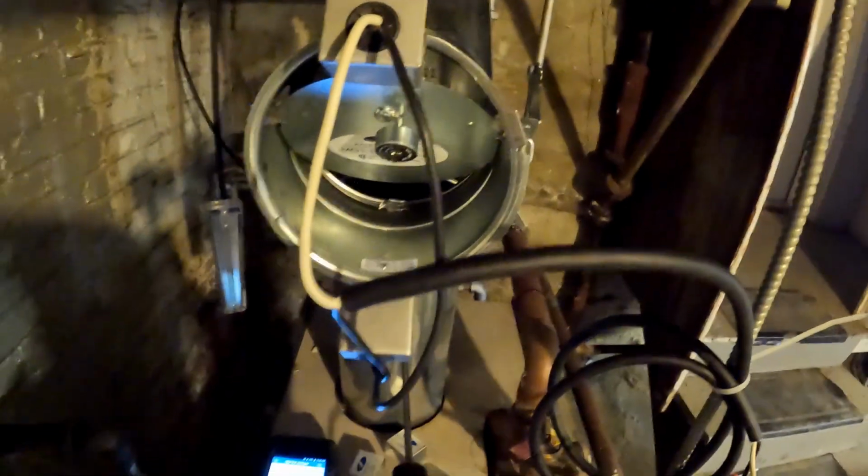And this is how this thing is working. We're at 4 parts per million. Steady state. It's not increasing or lowering, only going between 4 and 5. Of course, the draft is a little bit high, but that's because it's induced.